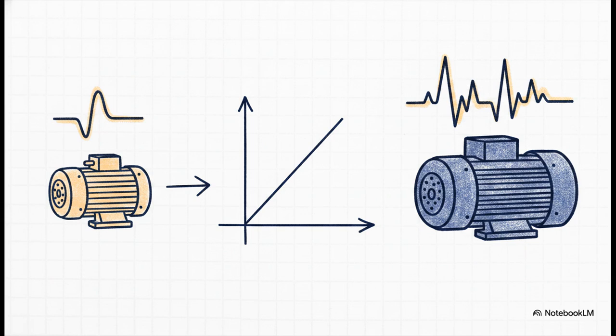Well, here's the crucial takeaway. Harmonic current is directly proportional to line current. If you double the current, the harmonic distortion predictably doubles right along with it. They scale up together. A bigger drive pulling more current simply generates proportionally more distortion. And why is this such a big deal for marine engineers? Because it's entirely predictable. It's a direct, linear relationship, not some wild, rogue variable that scales unpredictably when operations get heavy. That predictability is exactly what lets engineers design filtration systems with total confidence.